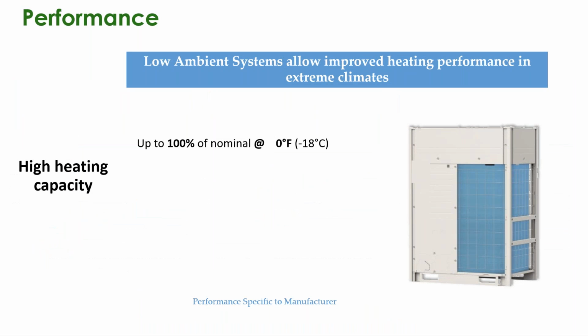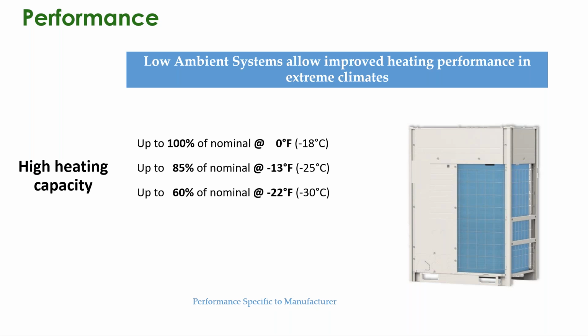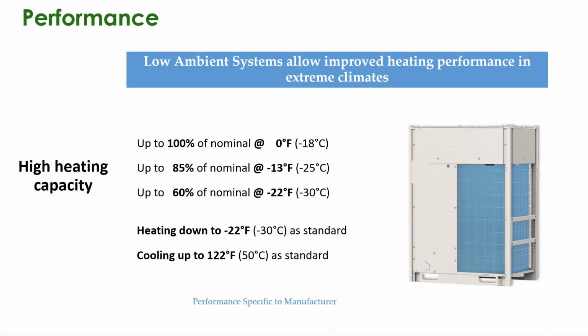These allow vastly improved heating in cold climates, up to 100% of your nominal rating at 0 and up to 85% of nominal at -13, up to 60% of nominal at -22. Now you would think that these are going to be grossly oversized, but it is actually technology driven that is allowing these to provide that amount of heat at that lower temperature without being grossly oversized on the cooling side. Performance on these is going to be specific to the manufacturer of choice. Heating with some manufacturers down to -22 is standard, and cooling up to 122 is standard.